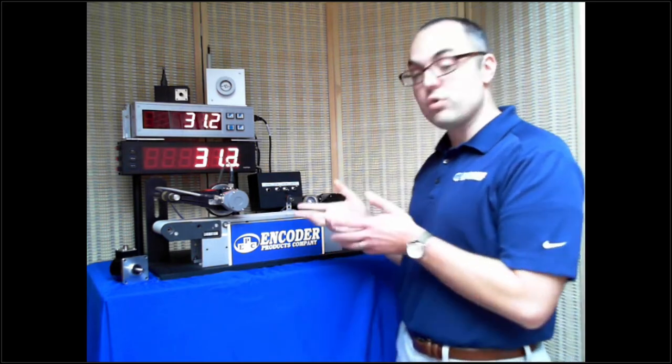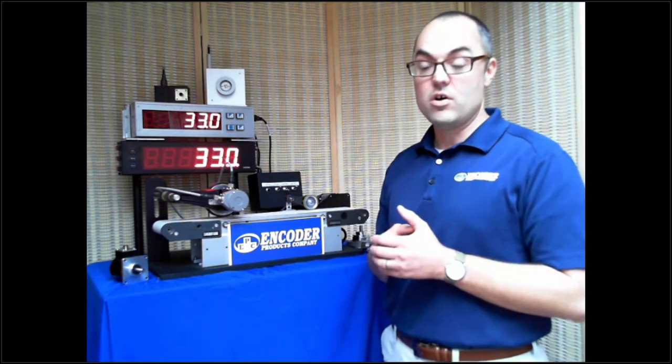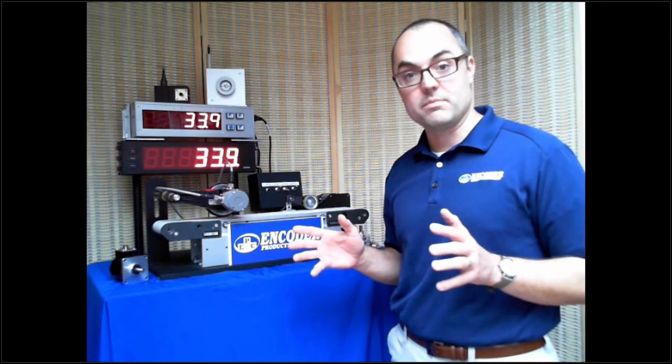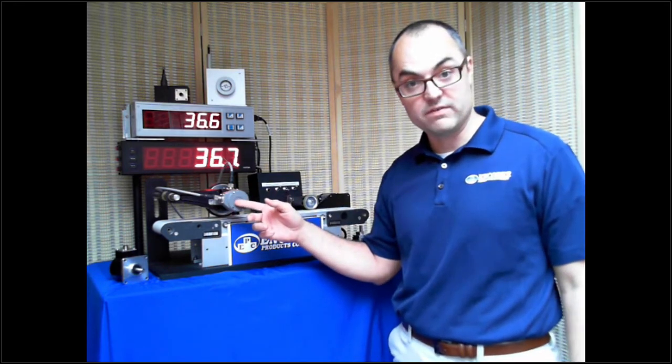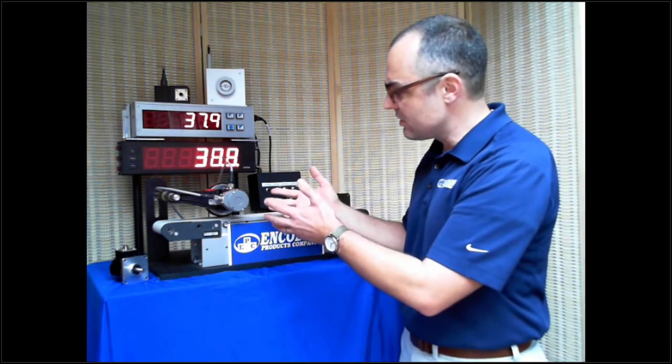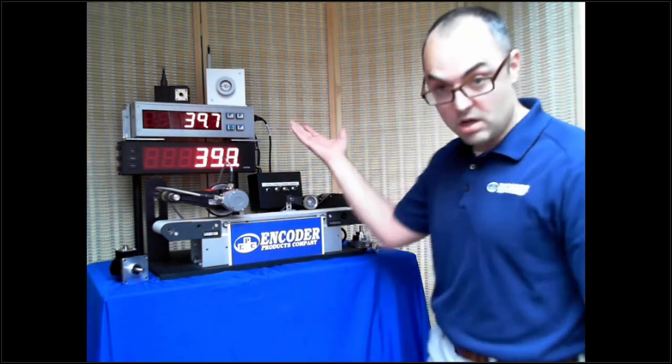That means that this encoder was still counting turns even when it was not plugged in. Our encoders work in the box. If you turn it when you receive it in the box, it's counting. An encoder with battery backup won't do that. The battery doesn't run the LEDs, it's not counting. All the battery's used for in the battery backup absolute encoder is storing the data, storing the position - it's not updating. So now you would have lost position if this was a battery backup.